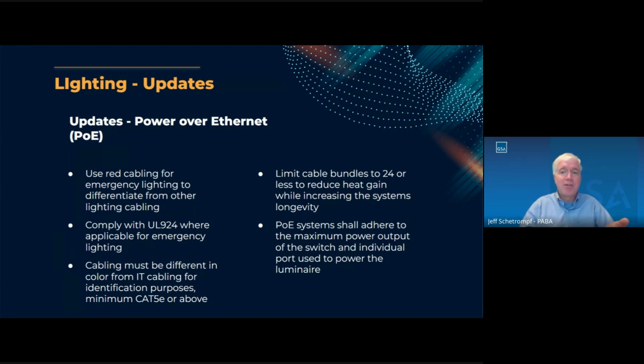Cable jacket colors is one of those items. For Cat5e and 6 cabling running all over the place, we wanted to ensure that PoE systems can be quickly distinguished from the cabling for your communications data drops for your computers and whatnot throughout the office. The easiest way to do this is simply to use separate jacketing colors. Beyond that, the emergency lighting will also be through separate IT switches than the other normal lighting for the space. We can segregate out those feeds by using red jacketing, just to let us know what's the emergency lighting versus the normal lighting.